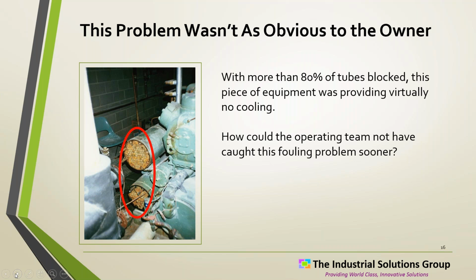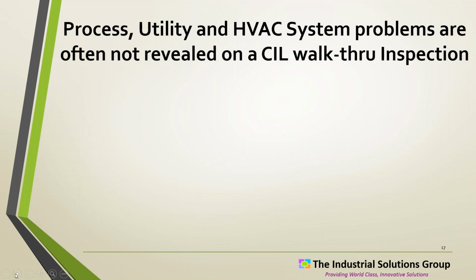So how could an operating team not have caught a fouling problem like this sooner? You really aren't getting any cooling, and they're having trouble keeping it online, and kind of going down the wrong path here on trying to get a fix for this particular chiller. Shouldn't they have known that? Why didn't they know that? And that's what we're going to talk about this afternoon. Try to get in the minds of the challenges that people have whenever they have to maintain equipment.